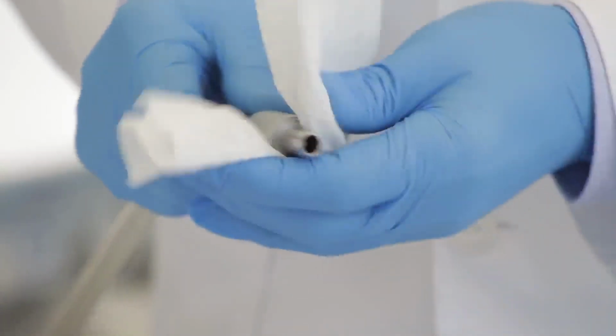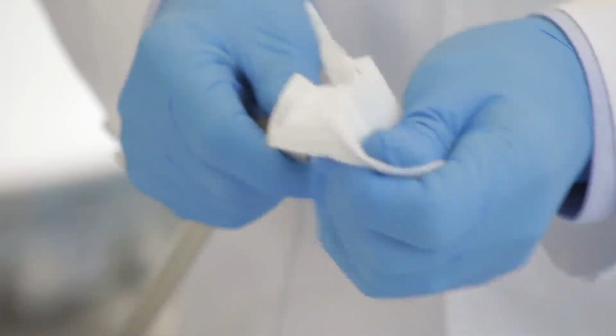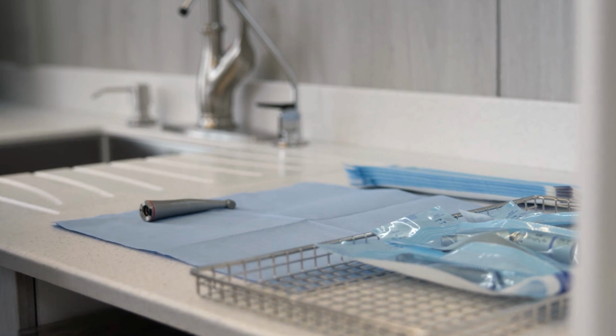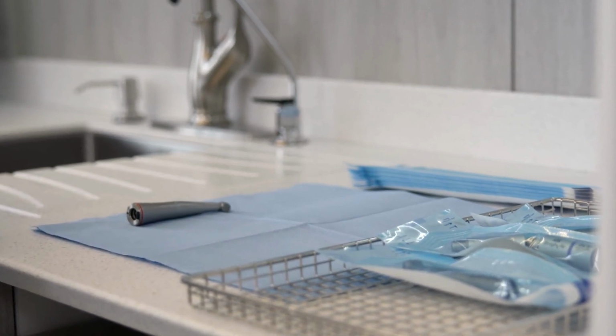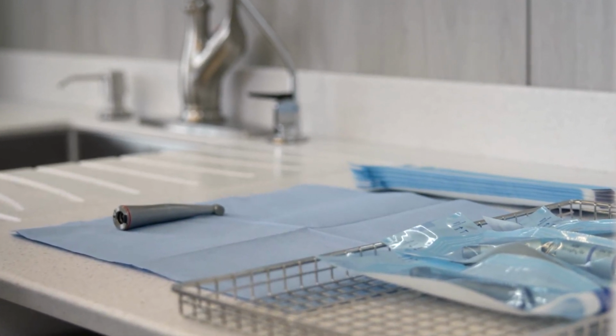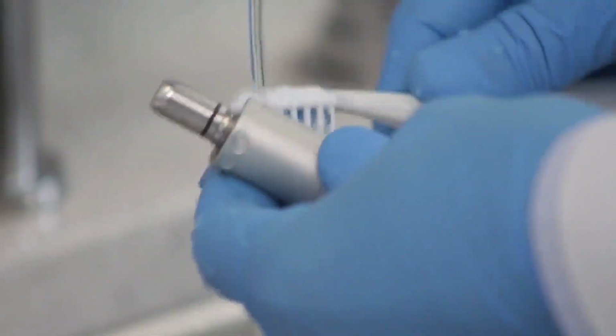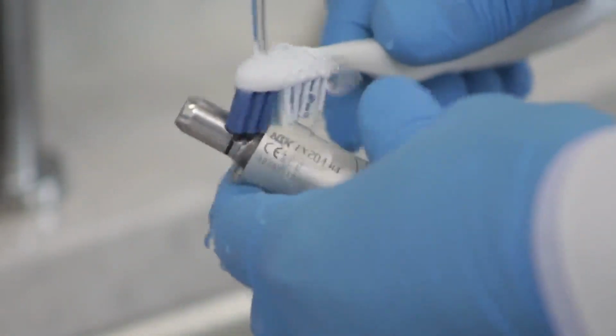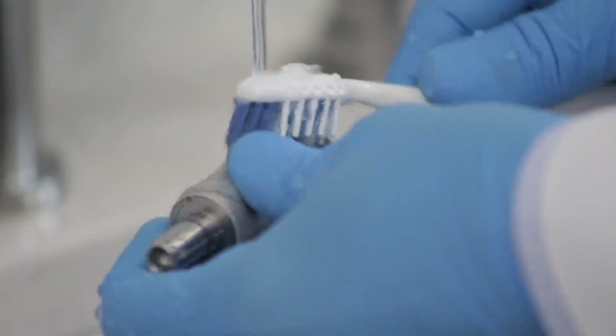Use disinfection wipes or an alcohol-soaked cloth to wipe the outer surface of the motor. Remove the motor from the tubing and take it to the contaminated area of the sterilization room. Thoroughly clean the external surface of the motor with a soft toothbrush under running water. Wipe it dry with a paper towel.